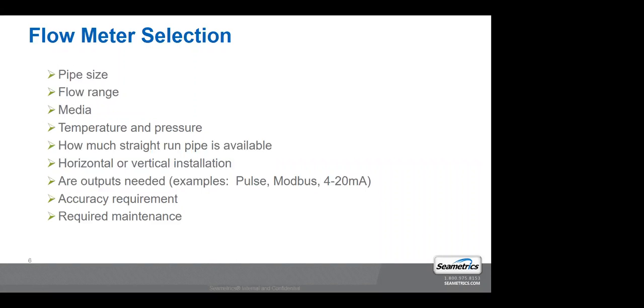When you select a meter, it's really as simple as going through a checklist of what is the pipe size that the water's flowing through, what is your flow range. Most meters have a minimum and max flow range that they operate within. What is the media? In irrigation, it's typically just clean water. You might have a little bit of sediment in it, but it's usually well water. Temperature and pressure, is it ambient? What's your pressure? Typically it's under 150 PSI range when we're speccing a meter in irrigation.